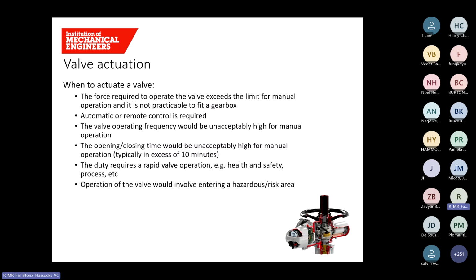When manual operation would take too long, typically more than 10 minutes, potentially impacting process performance. When fast valve actuation is critical for safety, emergency shutdowns, or dynamic process control. Or when manual operation would expose personnel to unsafe or restricted areas.